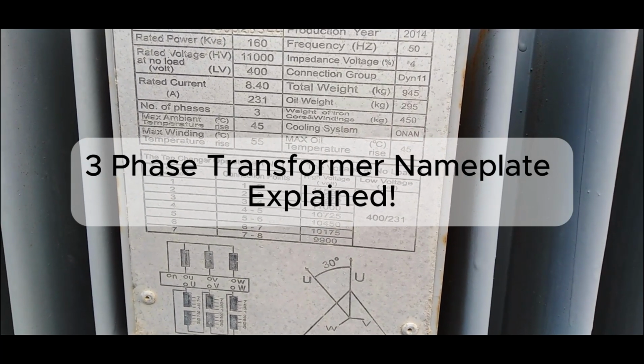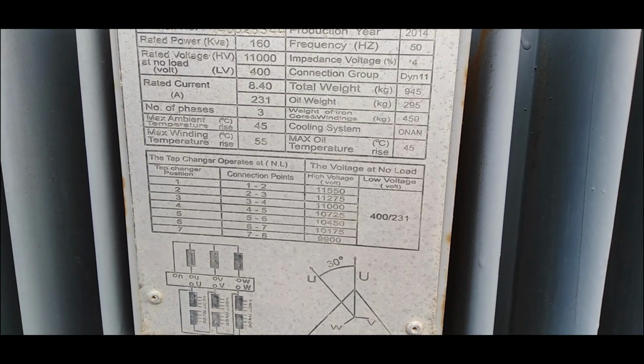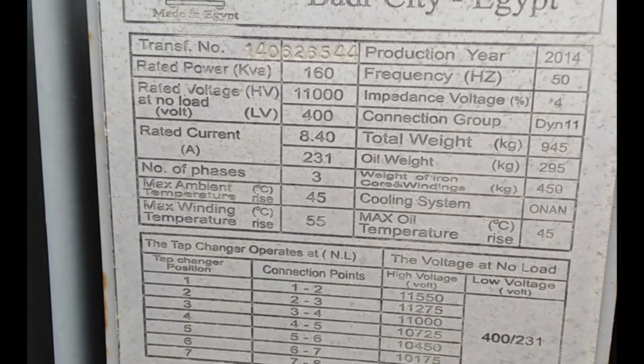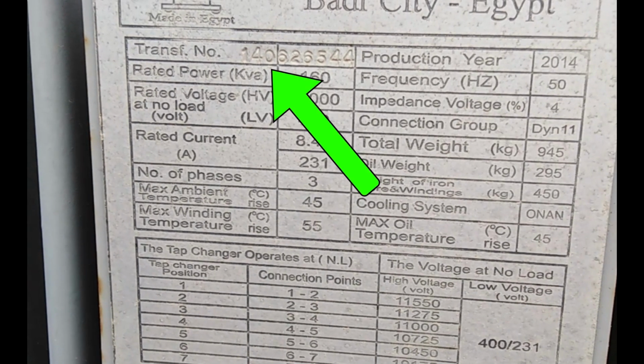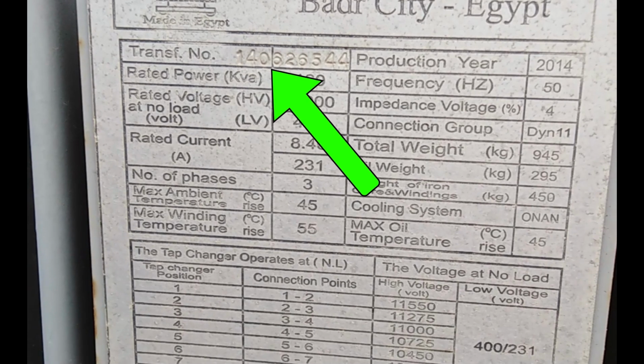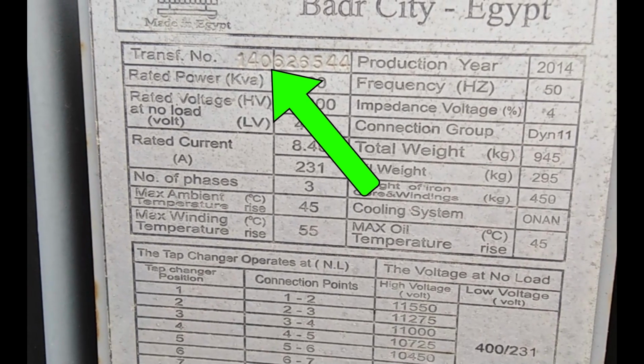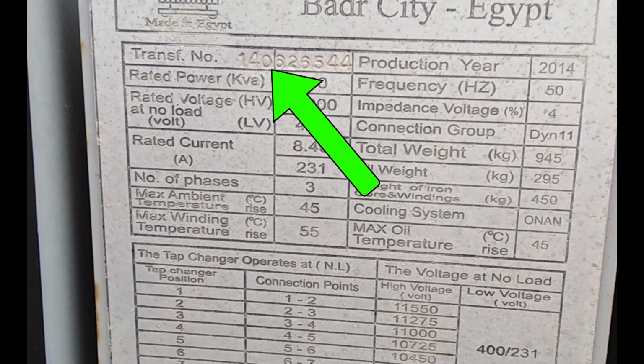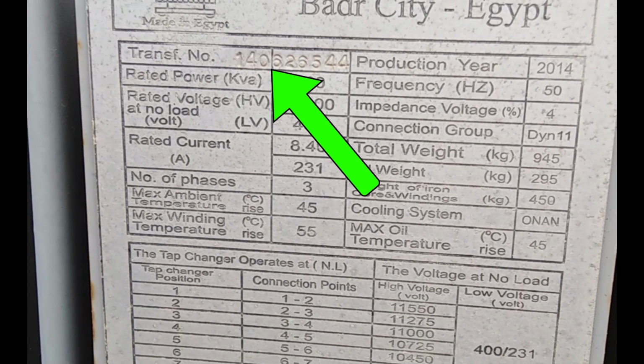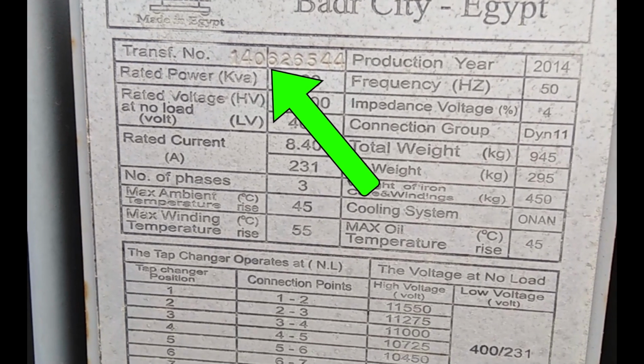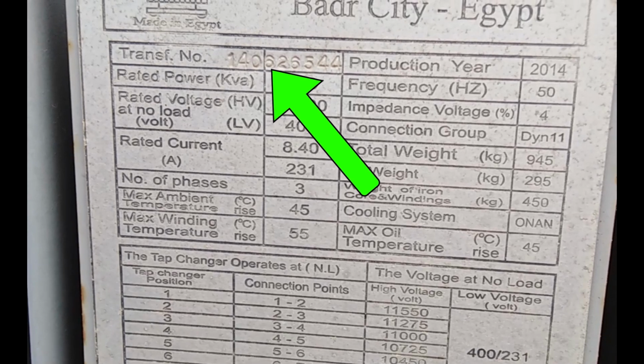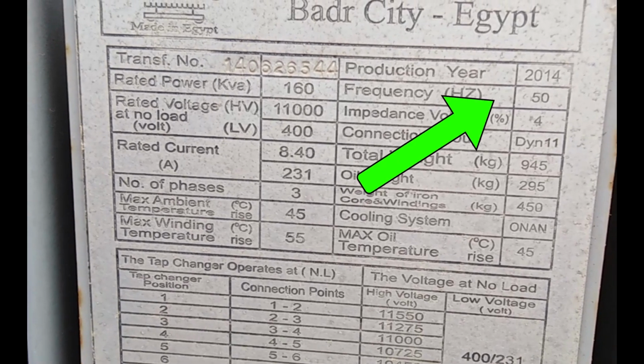So here we have the nameplate of a 3-phase transformer. This little plate is packed with crucial info that tells us everything we need to know about our transformer. Let's break it down. First up, the transformer number. Think of this as the transformer's ID card. It's unique to each unit and is super useful for tracking, maintenance, or when you need to get in touch with the manufacturer. Next, we have the manufacturing year, 2014 for our transformer.